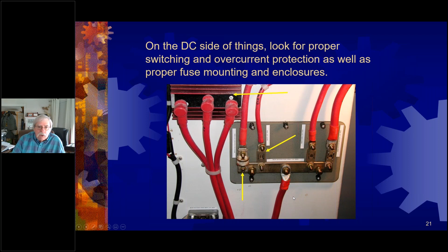Another issue here is in the upper left, you're looking at a diode type battery isolator, and those cooling fins are there for a reason. These things get hot. And the issue here is that it's mounted incorrectly for maximum thermal heat exchange. You would want these fins going vertically if you were trying to achieve maximum cooling potential. Heat rises. The way it's installed right now is some of that heat is going to get trapped between the fins and it won't rise away. So just a small consideration, an easy recommendation that I would make, because these devices, I can tell you, have historically a very high failure rate due to overheating. And anything you can do to help mitigate that as a potential problem is an easy recommendation on a survey report.